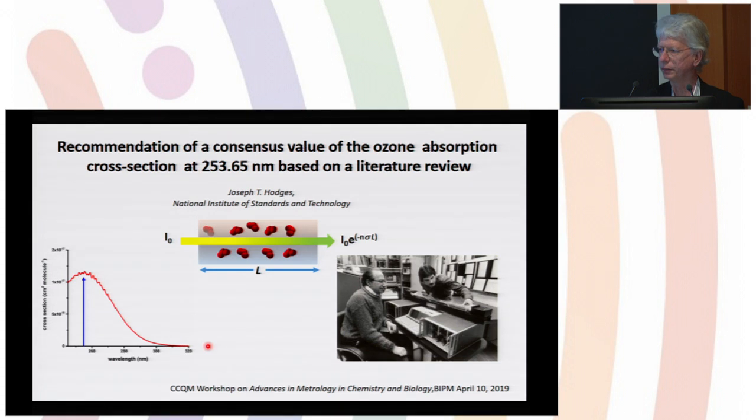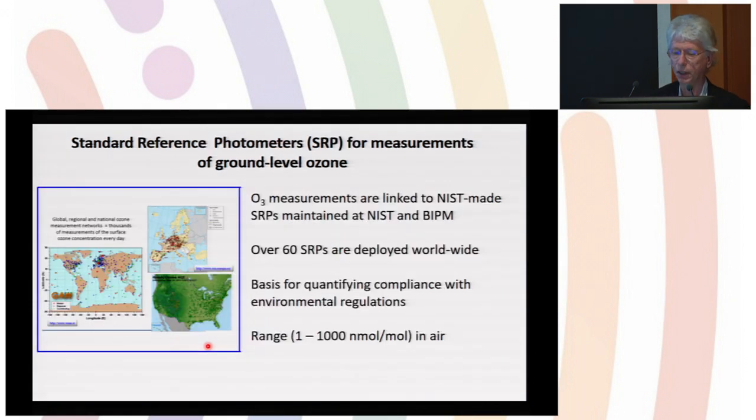The effort revolved around answering a very well-defined question: let's come up with a better value for the absorption cross-section of ozone at 254 nanometers. The reason we need this is because all tropospheric ozone measurements in the world to support regulatory and compliance issues are based on this developed instrument called the Standard Reference Photometer.